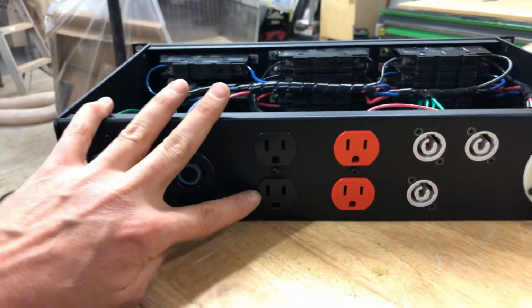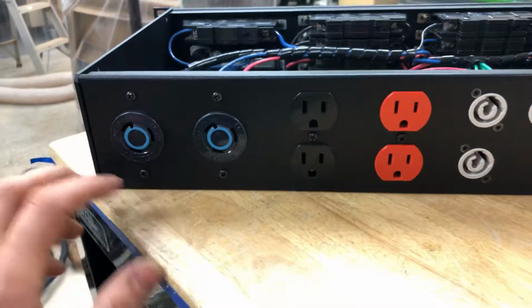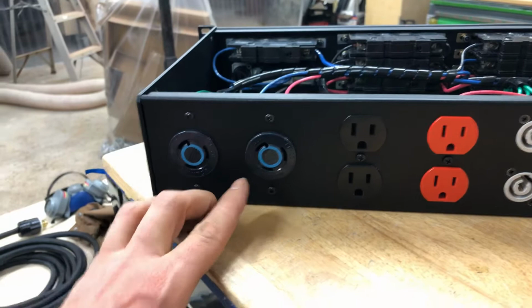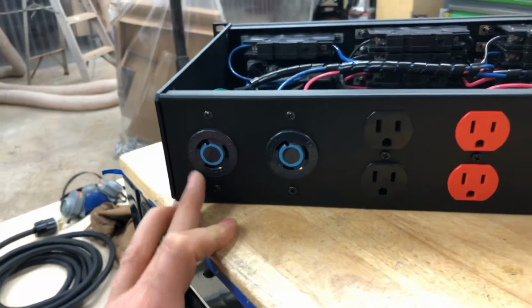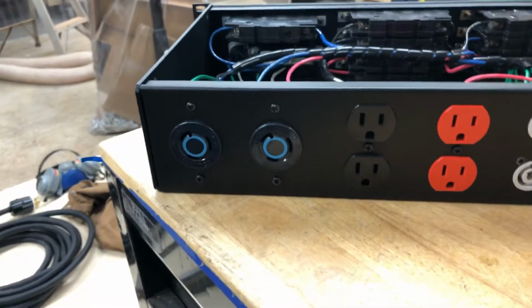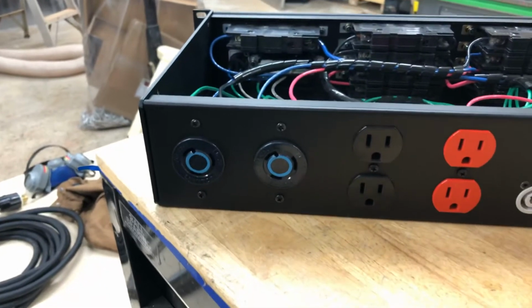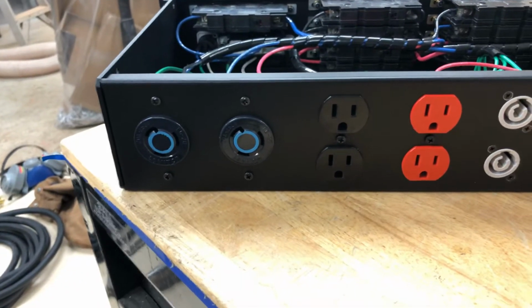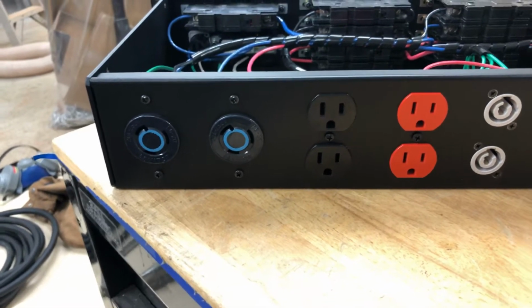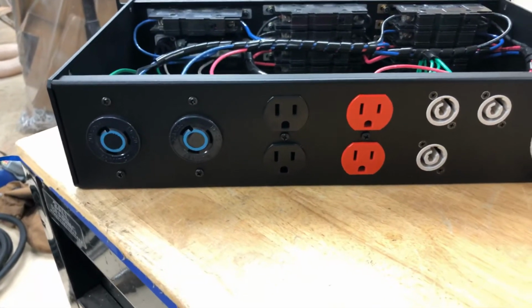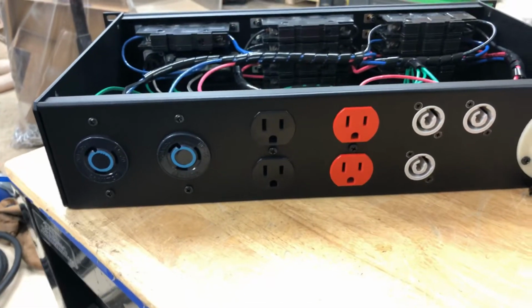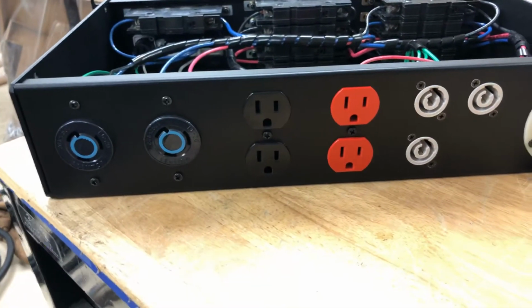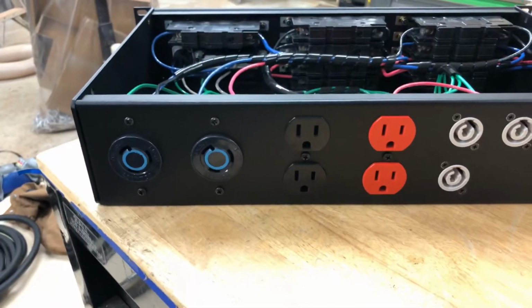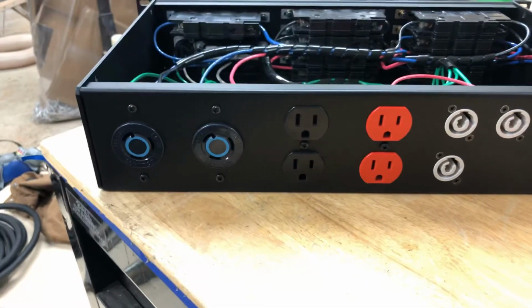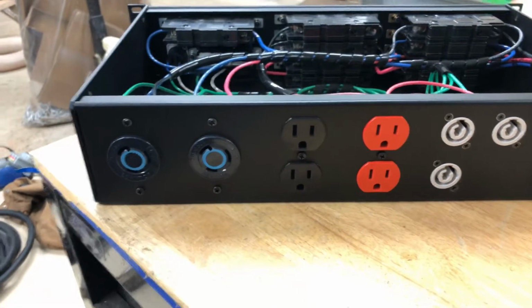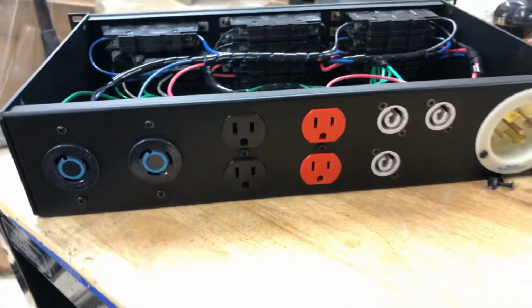Each of these 5-15s here is a dedicated circuit, and then I also have two 240 volt L6-20 twist locks for my larger amplifier application. That isn't strictly necessary because the amplifiers could use 30 amps at 120 volts instead of 240, but I had these plugs and receptacles already in stock, so I decided to go with a 240 volt option.